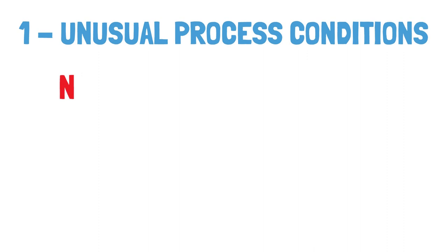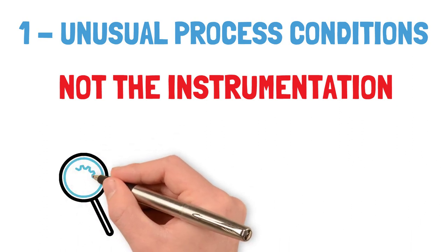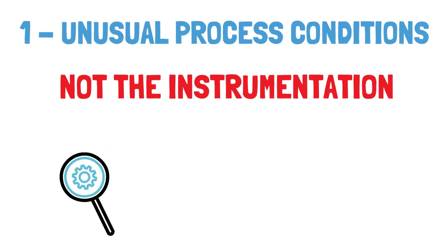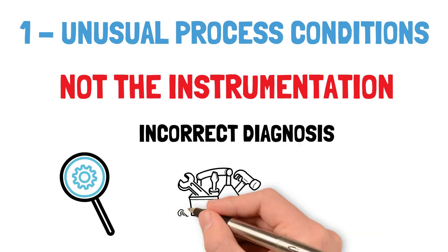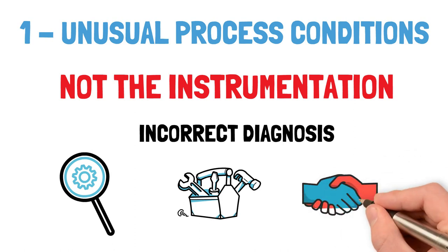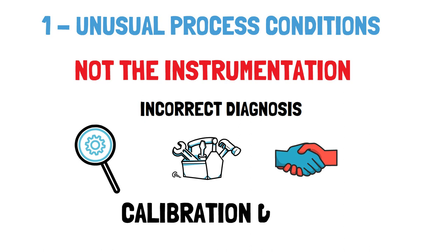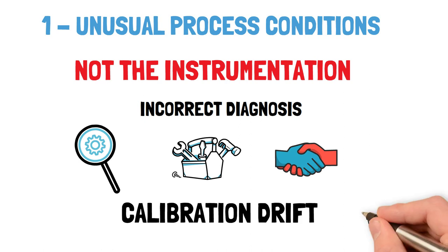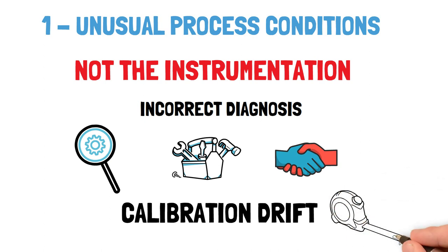Unusual or unexpected process conditions. As you will find out as an instrument technician, often a reported instrument failure isn't a failure at all. Unusual process conditions such as higher or lower pressures or levels may lead an operator to report a fault — you will often test the instrumentation to find it is operating correctly and that the problem is process related. Always try to work with your plant operators to discount any unusual process conditions before diving into fault finding. Other times, calibration drift of the instrument might be causing the unexpected readings. If this is suspected, calibrating the equipment either in situ or back at the workshop with calibrated test equipment will help restore trust in the instrument reading.